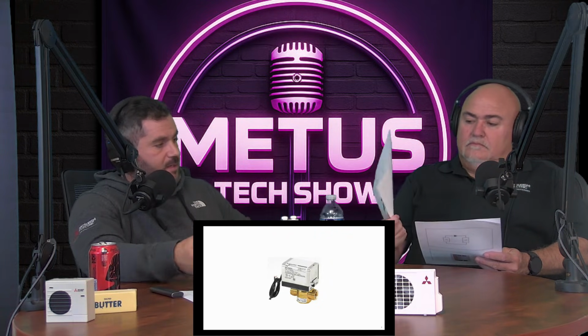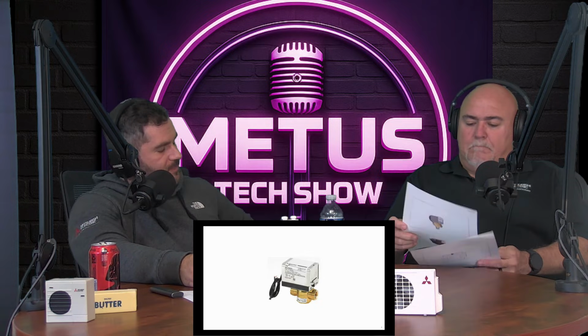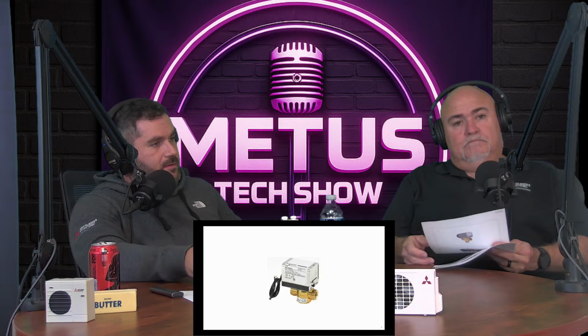This is a zone valve. This would be your 2-way, where it's an inlet and an outlet right here. Yep. It's an inlet and an outlet. And essentially, this is a 2-wire lead. So when a thermostat calls, it may send a 24-volt signal out to open up this.